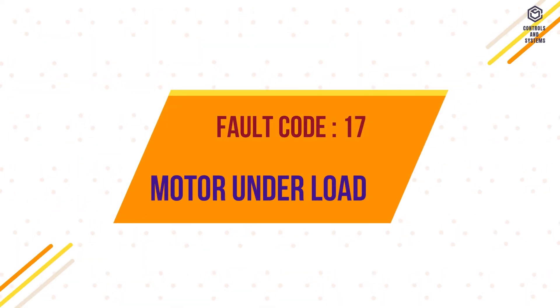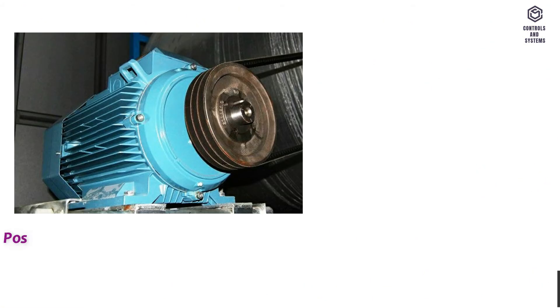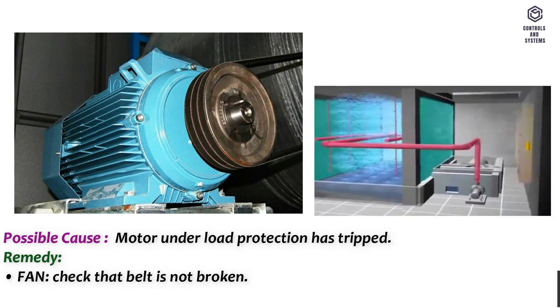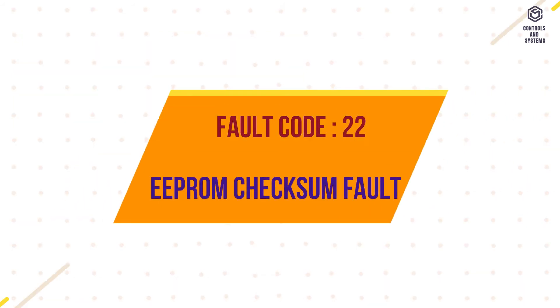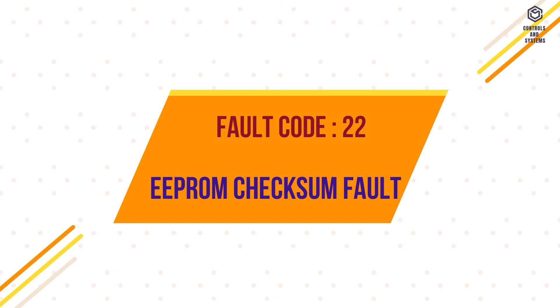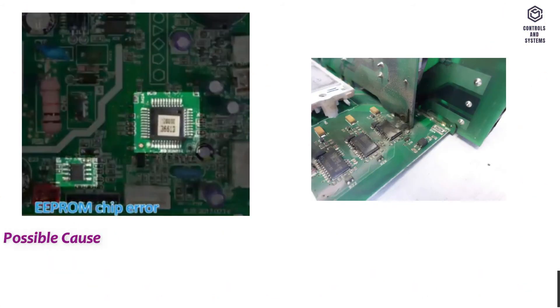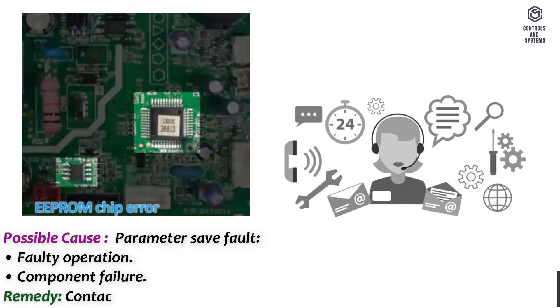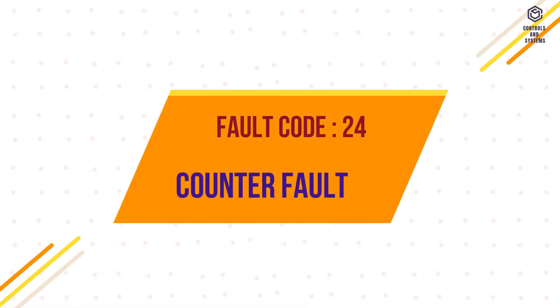Fault code 17 – Motor under load. Possible cause: motor under load protection has tripped. Remedy: for a fan, check that the belt is not broken; for a pump, check that the pump is not dry. Fault code 22 – EEPROM checksum fault. Possible cause: parameter save fault, faulty operation, or component failure. Remedy: contact technical support.